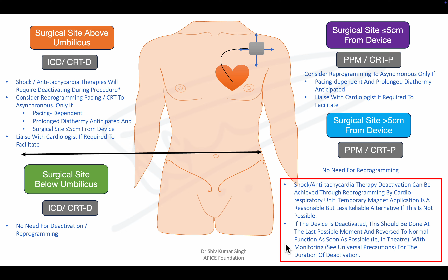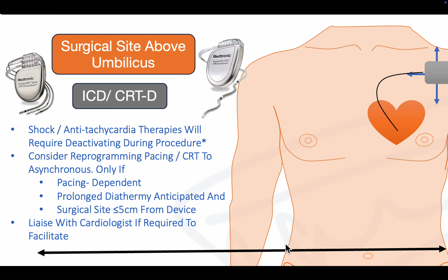If the surgery is above the umbilicus and the device is an ICD or CRTD, the shock or antitachycardia therapy needs to be deactivated during the surgery. You need to consider reprogramming the pacing of the CRT to asynchronous mode only if the patient is totally pacemaker dependent, there is prolonged diathermy used by the surgeon, for example for cutting, and the surgical site is less than 5 centimeters from the pacing device. So liaise with your cardiologist or the cardiorespiratory team for the reprogramming or deactivation.